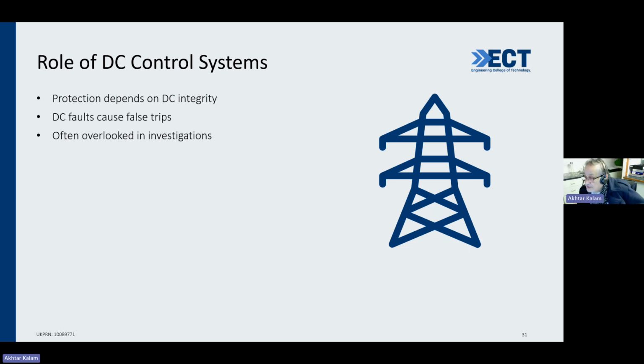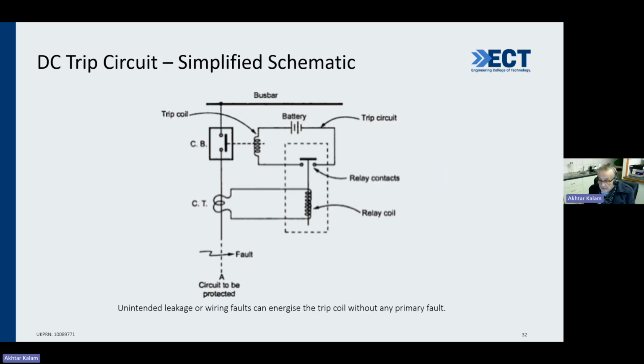So this is a question of the integrity of the DC. It's a question of a DC fault causing the trip, and the trip is false. And in most cases, an engineer will overlook this. For those who are very keen to know what happens, I've explained how the DC trip circuit works, because any unintended leakage can energize the trip coil. There's no primary fault, but it is still energized because of that leakage or the wiring faults.